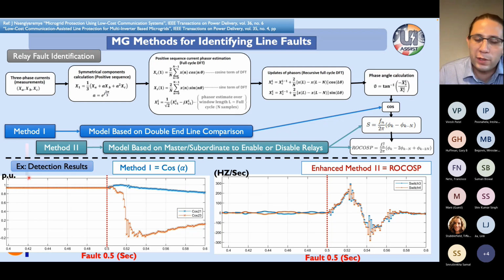Maybe some people will think it's a power factor, but because we are using the positive sequence, we decided to keep it as a per unit and unit-less system. And as we can see, these are measurements at both ends of the line. So the blue line is showing the left-hand side end, and the orange one is showing the right-hand side end. And we can see that when there is a fault, we are able to detect it through this algorithm.